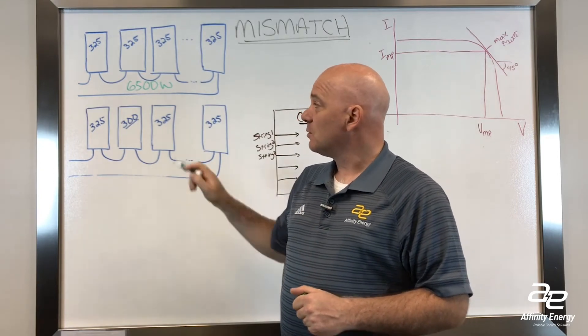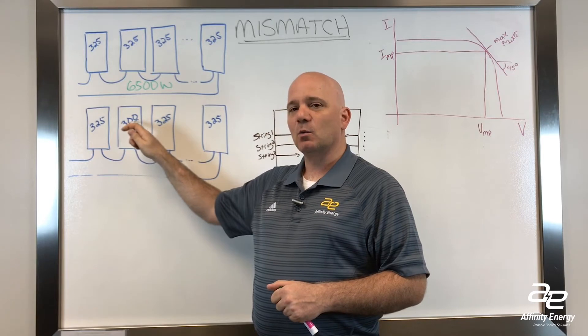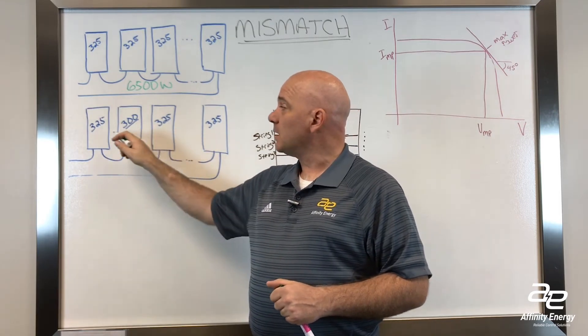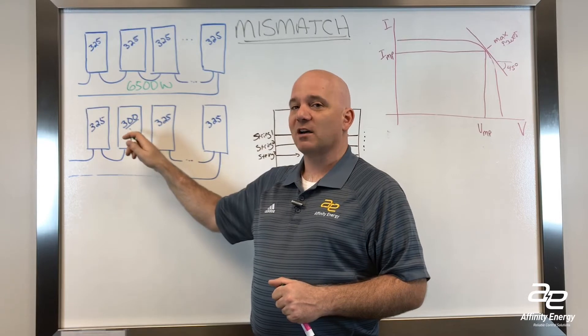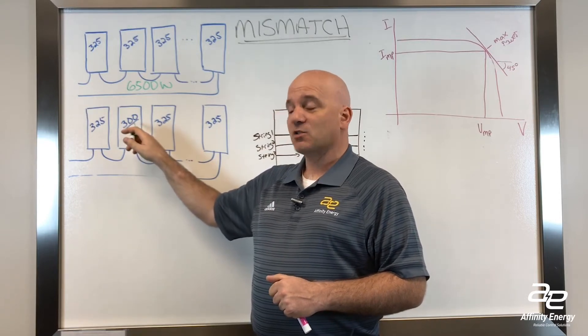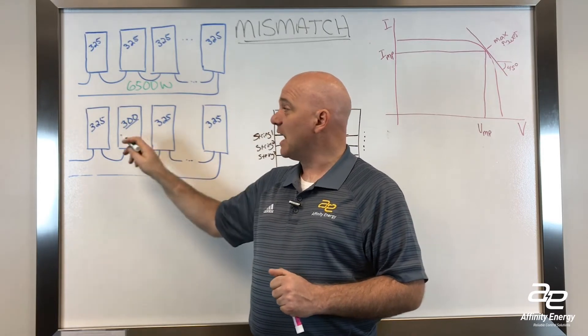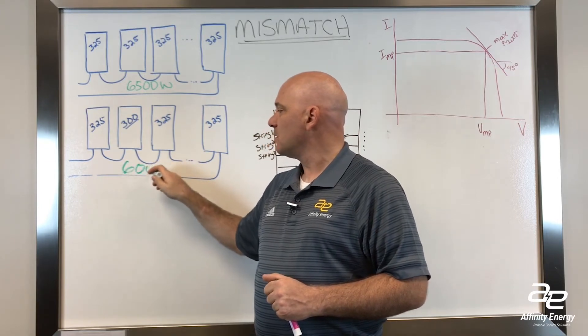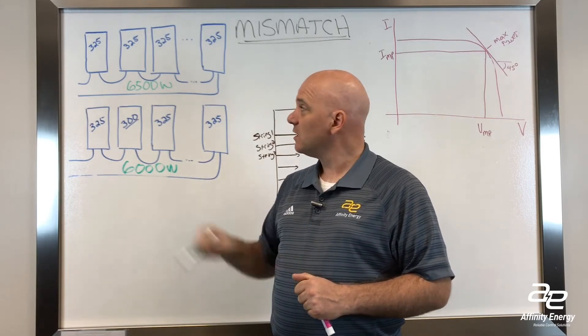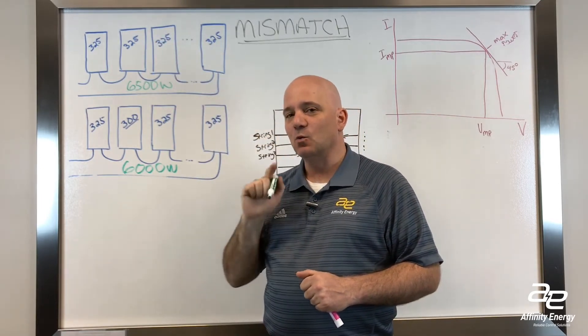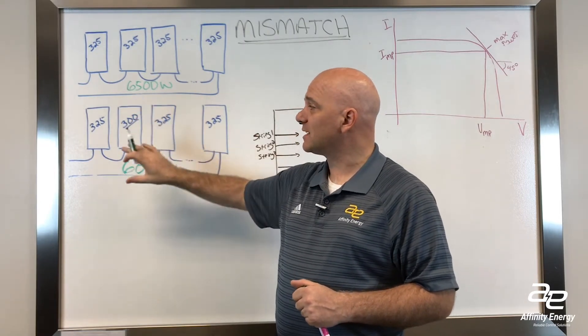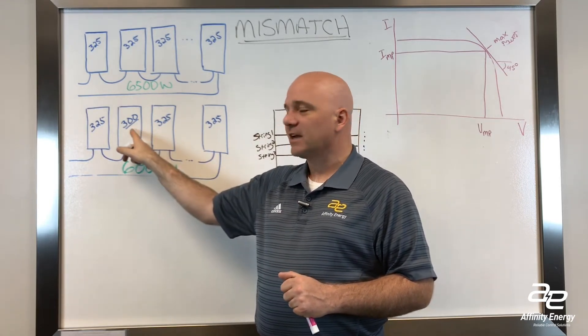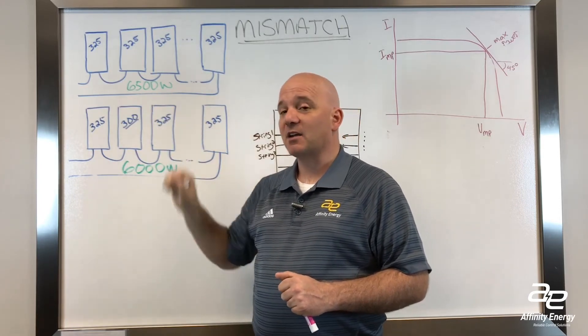Module mismatch means that if somewhere in here we've mixed in a 300-watt module instead of a 325-watt module, the difference is not just a 25-watt loss in power. That 300-watt module actually brings all the other modules down to its level, and now we've got 20 modules at 300 watts, or 6,000 watts — a 500-watt loss, even though there's only a 25-watt difference in one module in the string. So it's very important to keep modules of the same bin class together in strings, because one little tiny error is going to have a significant impact on the amount of power that comes out.